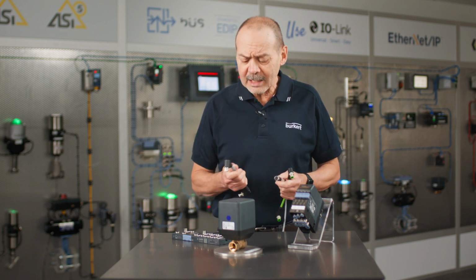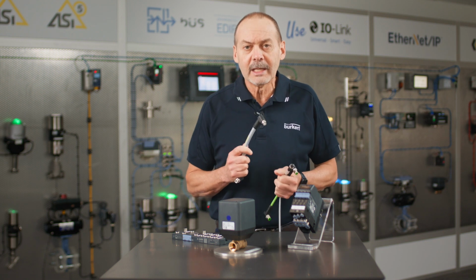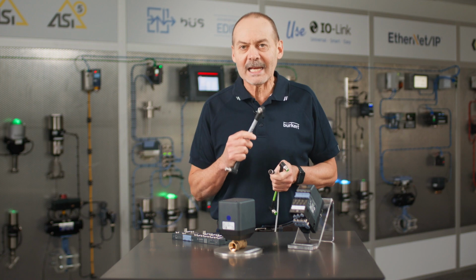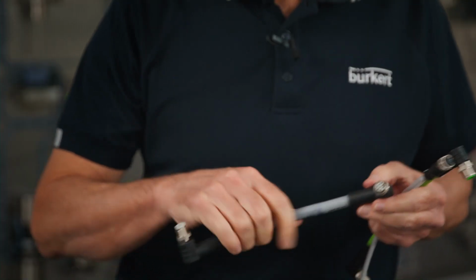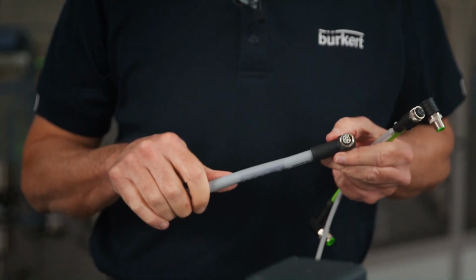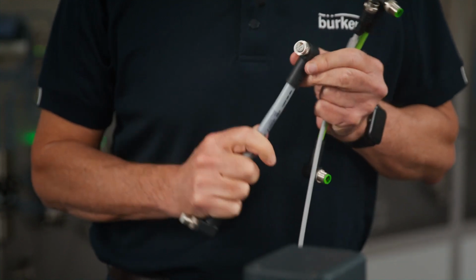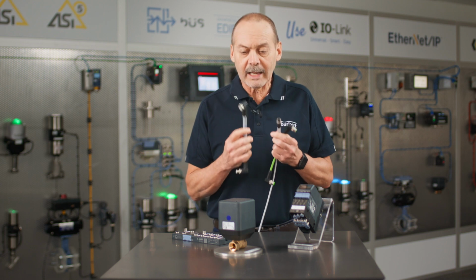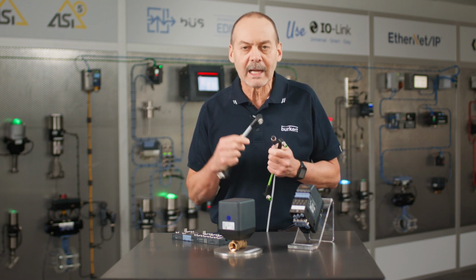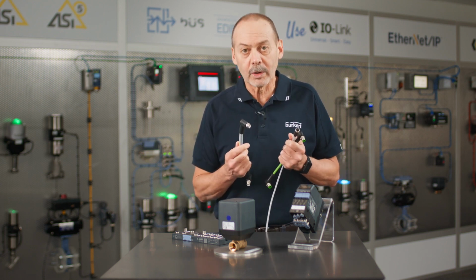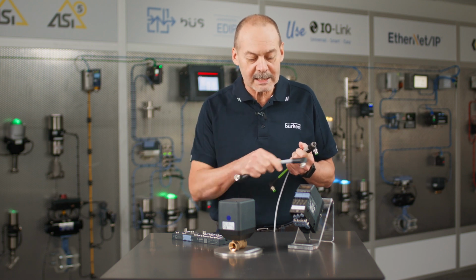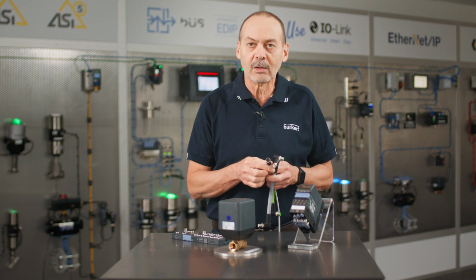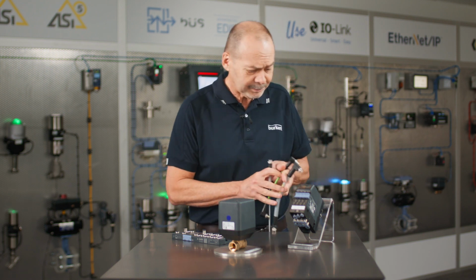Another one that's fairly new to the market is the L-coded. Now this is a power cable that can take up to 16 amps. So it's generally used for connecting power to the different blocks and things in the field. There's a number of different types, as you can see, right angle and straight, and it depends on your block and how they are all keyed as to what works, and also on the particular sensors, whether the straight or right angle will sit out at a strange angle, or you need to use one or the other.